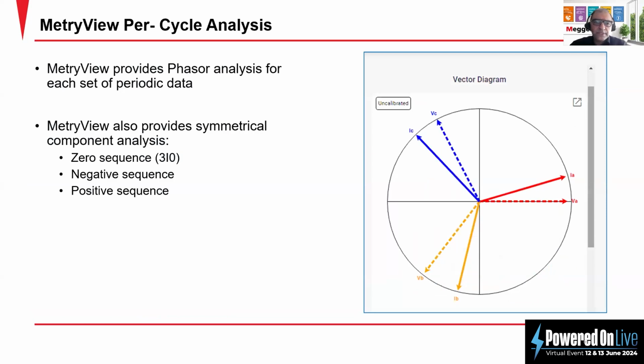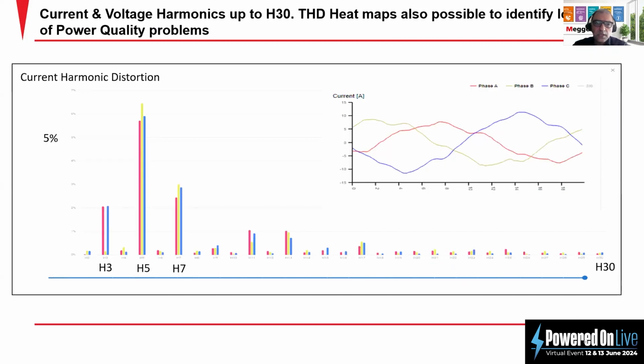It provides the per-cycle analysis for the phasor diagram, which gives you the voltage, current and phase angle, and also provides zero, negative and positive sequence, enabling the utilities to have more information about the high impedance faults mainly. It's measuring the harmonics, current and voltage, and total harmonic distortion, and harmonics up to the 30th. And this enables the utilities to identify the power quality problems.